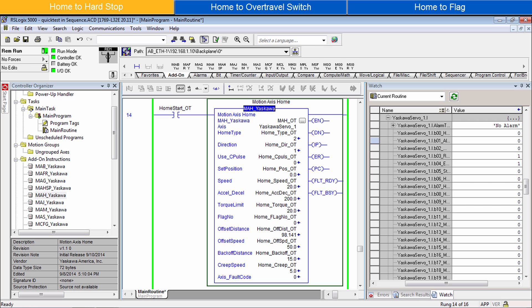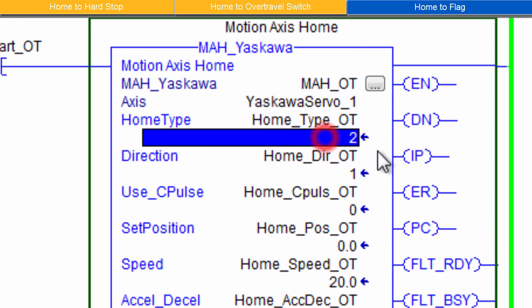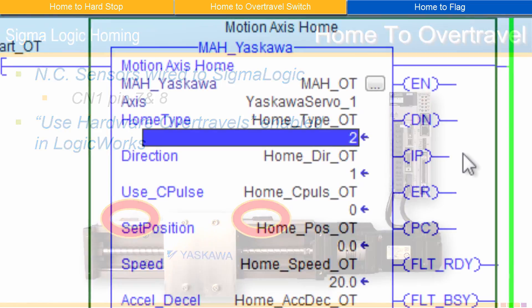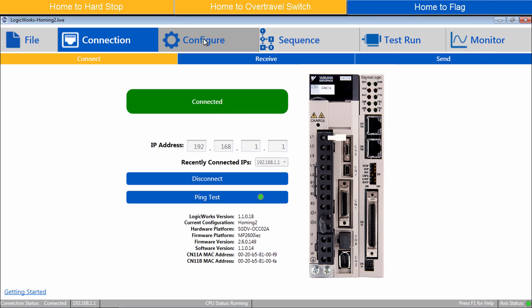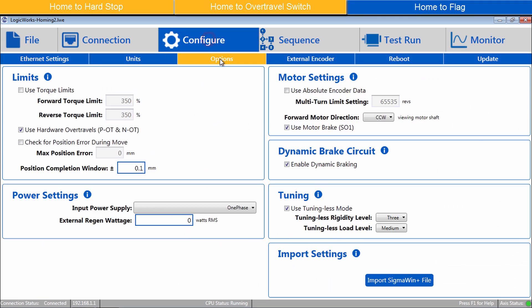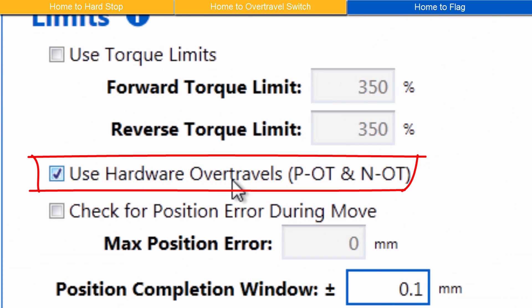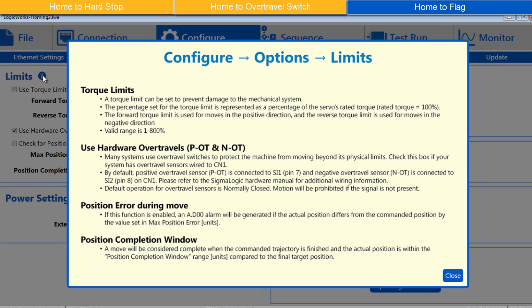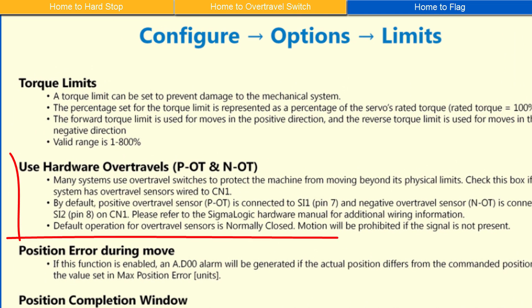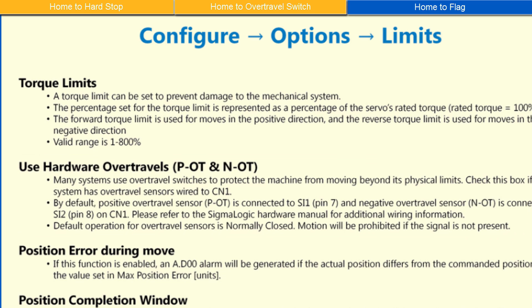Home to Over Travel Limit is Home Type 2. This Home Type applies to mechanisms with limited travel distance and over travel sensors. In Logic Works under Configure, Options, verify that Use Hardware Over Travels has been checked. Over Travels should be normally closed proximity sensors wired to Connector CN1, Pins 7 and 8.